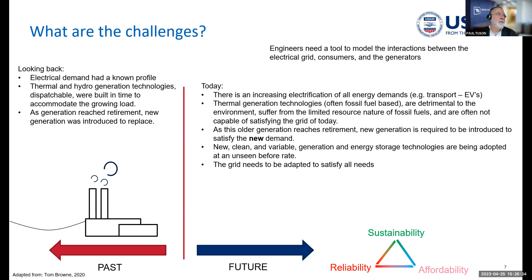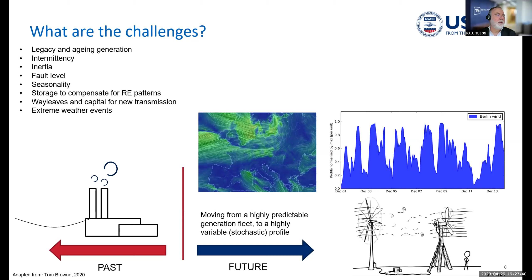Challenges of modern power systems include legacy and aging generation, intermittency from renewables, reduced inertia and decreased fault levels from inverter-based generation. Mitigation for decreased fault levels includes synchronous condensers, which provide inertia, dynamic voltage response, and fault level support. Other challenges include seasonality, storage to compensate for renewable energy patterns, way leaves and capital for new transmission lines and systems, and extreme weather events. Load duration curves and average load and generation are no longer sufficient; hourly stochastic analysis is now required for effective planning and operation of a power system.